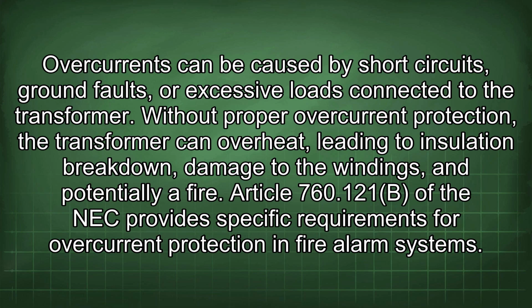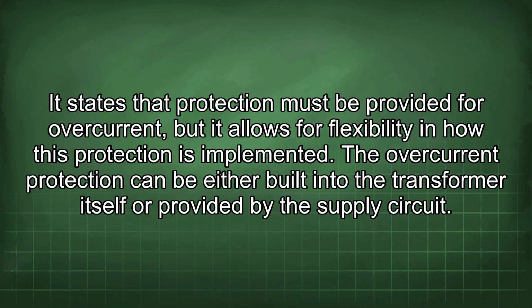Article 760.121(B) of the NEC provides specific requirements for overcurrent protection in fire alarm systems. It states that protection must be provided for overcurrent, but it allows for flexibility in how this protection is implemented. The overcurrent protection can be either built into the transformer itself or provided by the supply circuit.